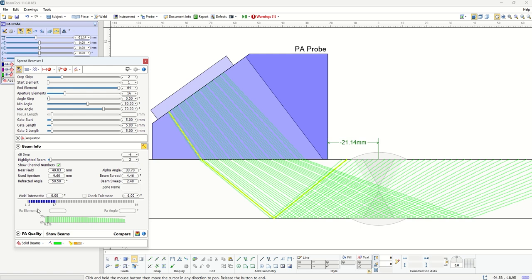If I keep moving, what you will notice is that as the angles increase, the aperture that's creating those beams is also changing. And also you will see that as this line is moved, the exit point on the probe moves toward the top. And also you can easily see what beam is hitting the weld bevel. That information is also here: whatever intersection angle we have between the beam and bevel is shown here. And ideally you want to be close to 90. For instance, for this beam, you see that's 85.